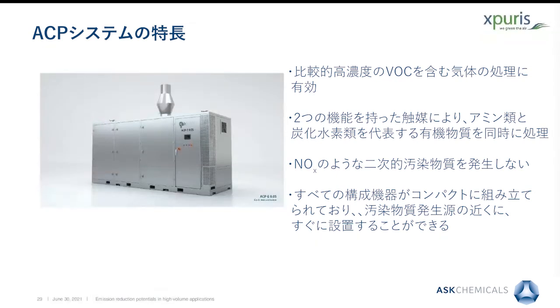Yes, just a few points to take into consideration. This system is for purifying air streams with high VOC concentrations, say 2 to 5 grams of VOC per normal cubic meter, up to 10 grams of VOC per normal cubic meter. And you remove amines and organics in one step due to the dual function catalyst.